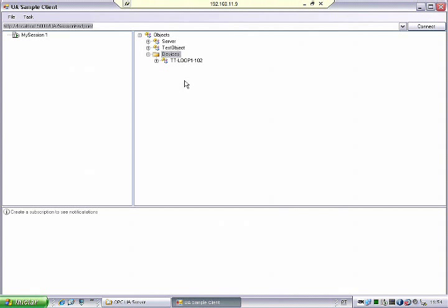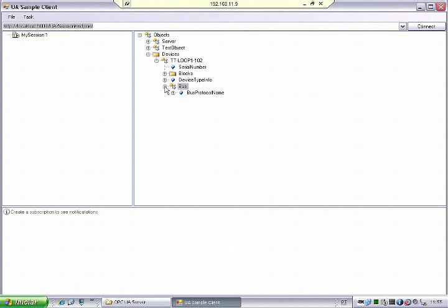What you are seeing right here is the OPC UA object representing this field device. The network driver added to the reference server is able to locate that device. It gets information from the device that enables the server to locate the device description — it retrieves the manufacturer, device revision, and description revision. Using that information supplied by the network driver, the server locates the description on the computer, and you can see properties, folders, and variables that the information model requires when creating a device object.